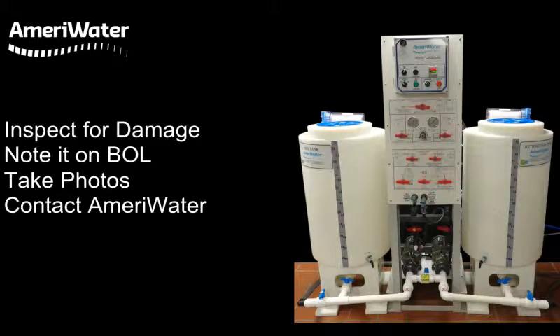When the bicarb system is delivered, immediately inspect the system for damage. Note any damage on the bill of lading. Take photos of the damage if possible and report it to AmeriWater.